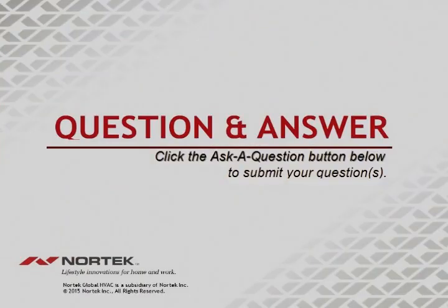Next question. Do you guys recommend having the furnace plugged into a 115 plug-in? Plugging a furnace into a 115 receptacle? Actually, no. We don't recommend that. It's done all the time. There's lots of places around the country where that is allowed, and they consider that a legal means of electrical disconnect. And here's the thing, guys. If the manufacturer did not specifically supply in the packaging of a furnace the means to be able to take, say, an extension cord and cut that thing off and then adapt a plug into it to take it to a receptacle, that's not a legal means of disconnect then.